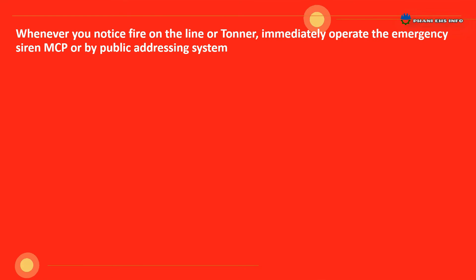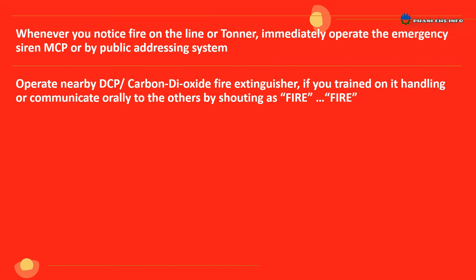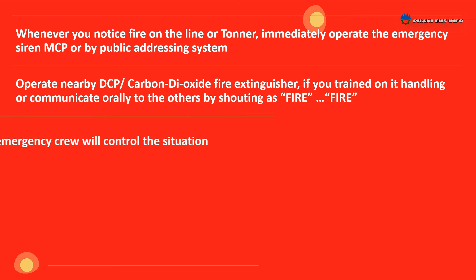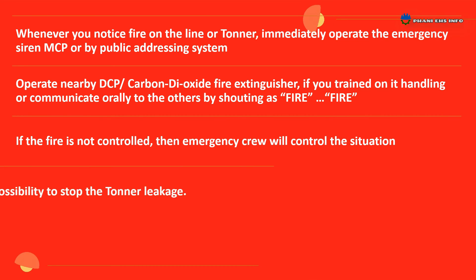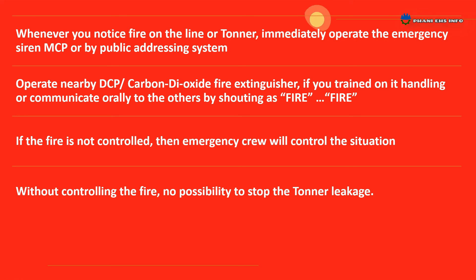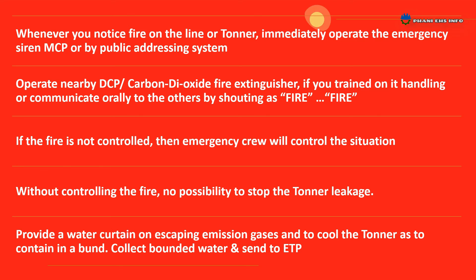Whenever you notice fire on the line or tonner, immediately operate the emergency siren MCP or by public addressing system. Operate nearby DCP or carbon dioxide fire extinguisher if you are trained in its handling, or communicate orally to others by shouting 'Fire!' If the fire is not controlled, the emergency crew will control the situation. Without controlling the fire, there is no possibility to stop the tonner leakage. Provide a water curtain on escaping emission gases and to cool the tonner, containing within a bund. Collect bounded water and send to ETP.